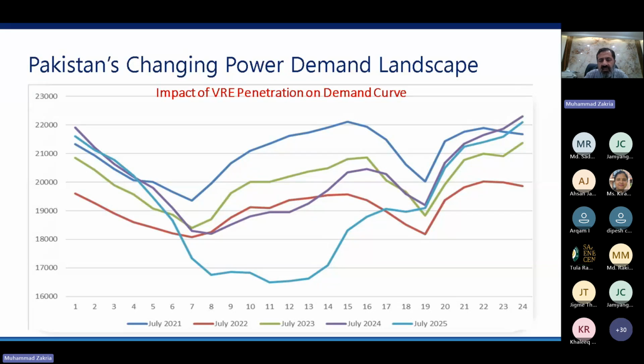Like on Eid al-Fitr this year, 2025, when I was in the control room during the Eid day, imagine our country's load demand came down to 6,000 megawatts, maybe even 5,800 megawatts. We maintained our system with just a single 500 kV transmission link due to over-voltages. What happened?